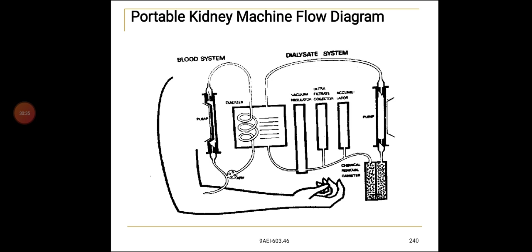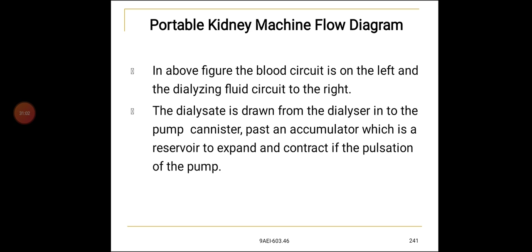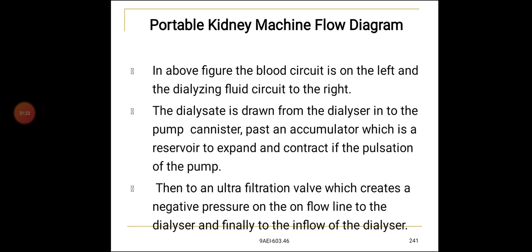Portable kidney machine flow diagram. In the above figure, the blood circuit is on the left and the dialyzer fluid circuit is to the right. The dialysate is drawn from the dialyzer into the pump canister. Past an accumulator, which is a reservoir to expand and contract with the pulsation of the pump. Then to an ultrafiltration valve, which creates a negative pressure on the outflow line from the dialyzer, and finally to the inflow of the dialyzer. The accumulator and ultrafiltrate reservoirs do not function when the tank is in the circuit, but are essential for use without the tank.